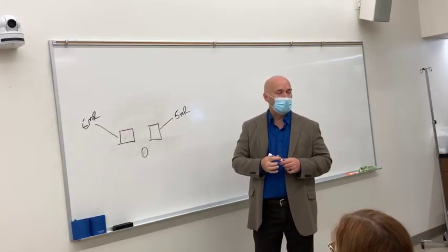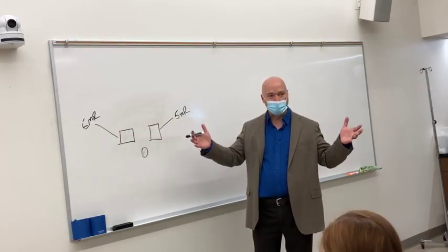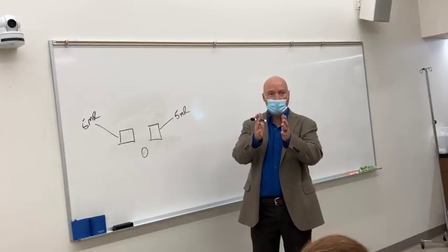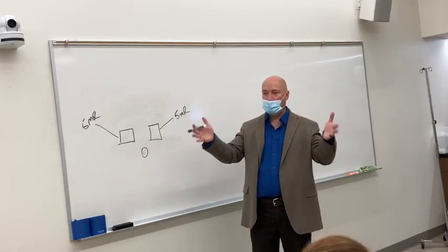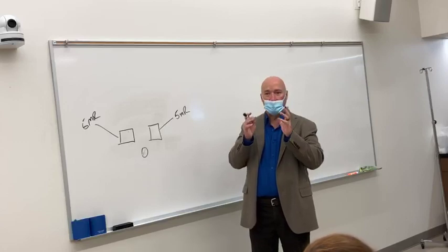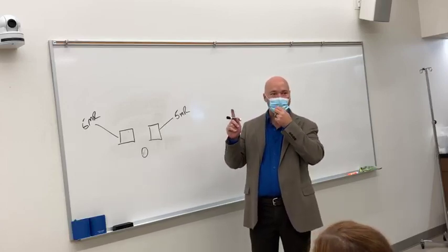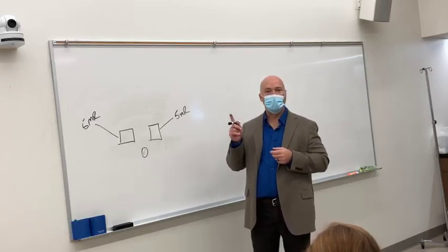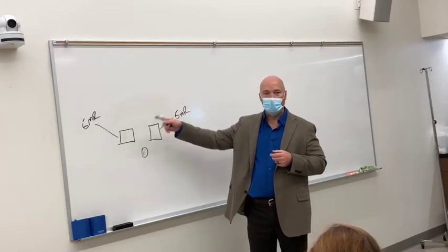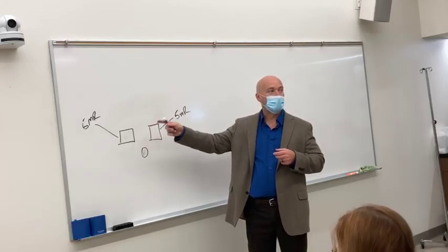5. Right. But I've got a thicker patient as opposed to a thinner patient. So what's going to happen with the thicker patient versus the thinner patient? If our mA is set, our kVp is set, what's going to change? The time. So these become your exposure timers.